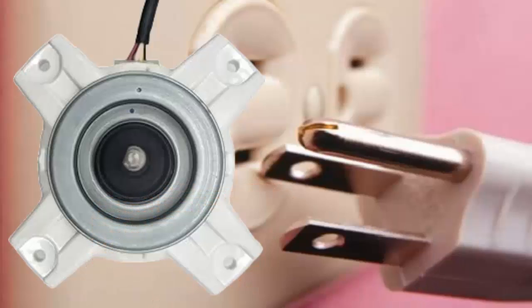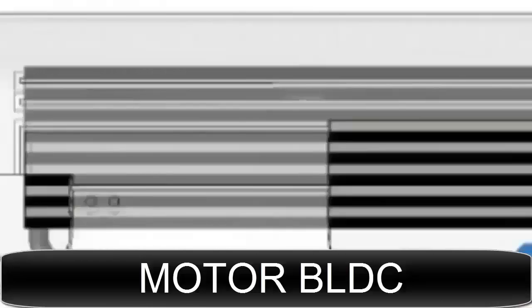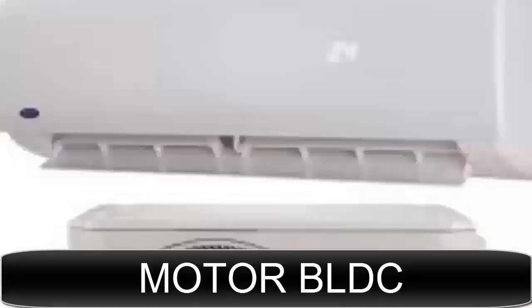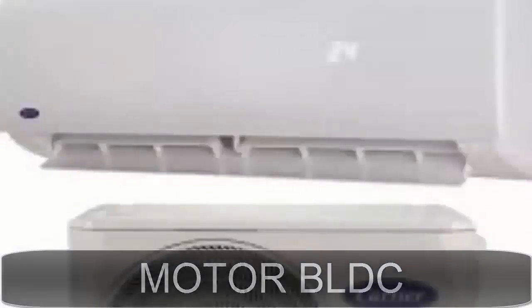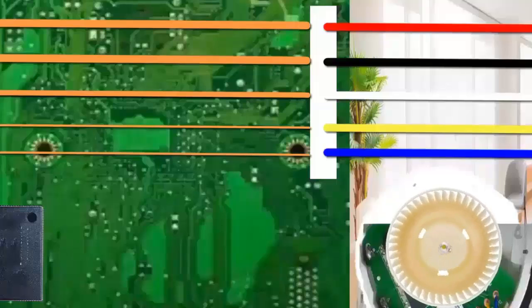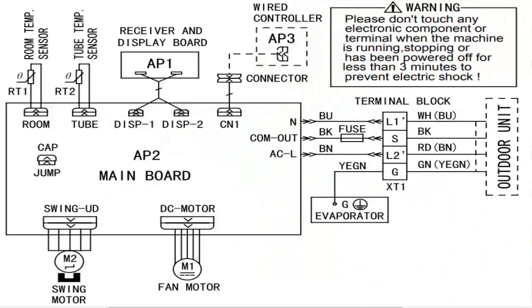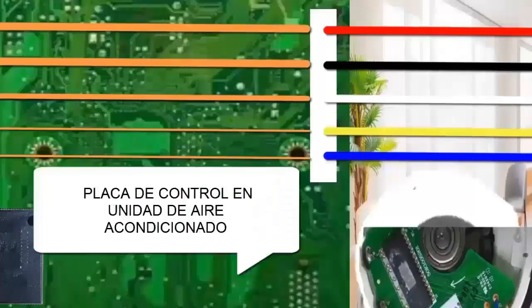Now, we will look at more specialized solutions for BLDC fan problems in Sharp air conditioning units. A. The BLDC fan can be used in both the indoor evaporator unit and the outdoor condenser unit. B. The indoor unit BLDC fan uses 5 wires, as the power supply to the motor coils is done within the casing via an independent internal electronic board.